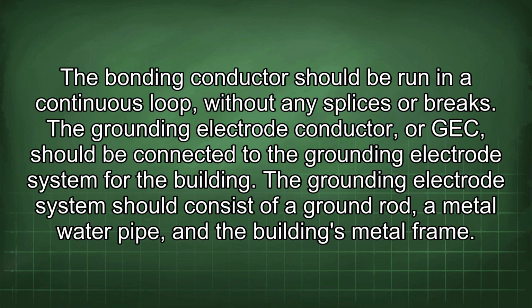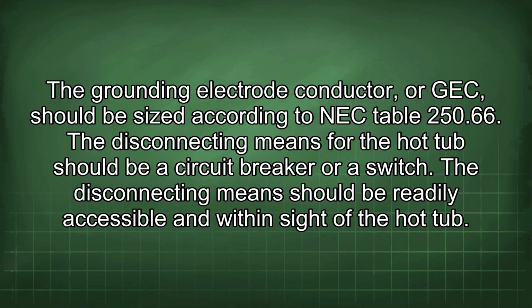The grounding electrode conductor, or GEC, should be connected to the grounding electrode system for the building. The grounding electrode system should consist of a ground rod, a metal water pipe, and the building's metal frame. The grounding electrode conductor, or GEC, should be sized according to NEC Table 250.66. The disconnecting means for the hot tub should be a circuit breaker or a switch.